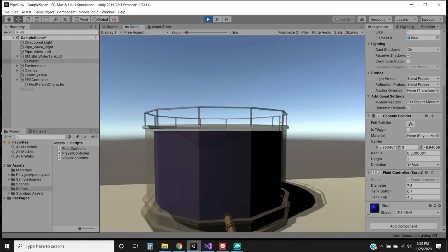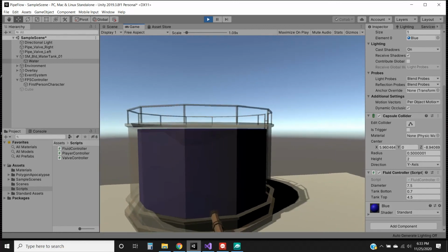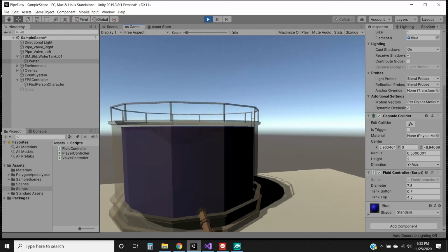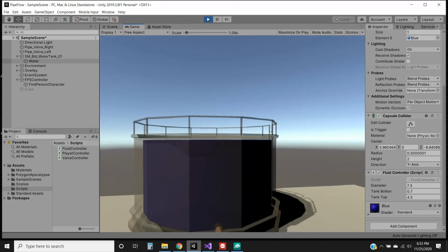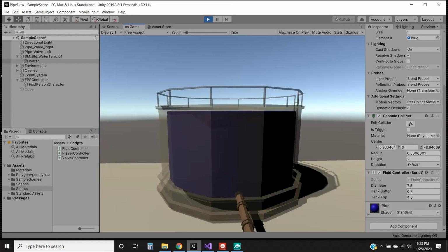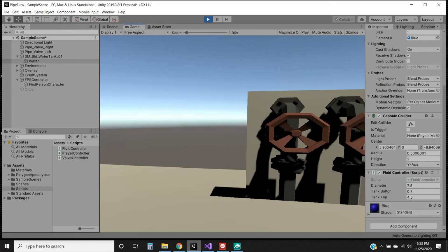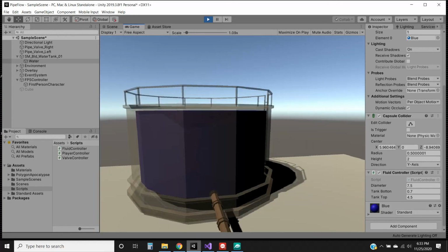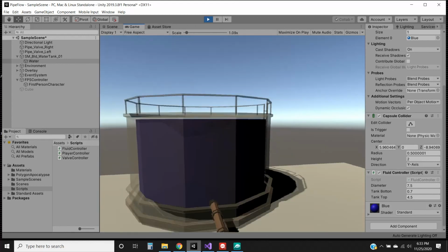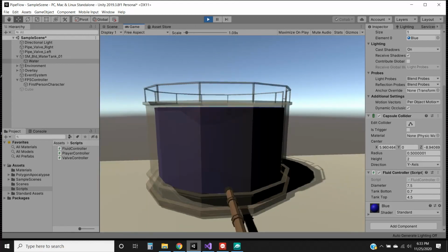One thing about this flow rate is that it's volumetric flow rate with constant head. So basically our flow rate is not changing at all during the course of this tank filling up. And that's a reasonable assumption, I think, when you have a city, municipal distribution system supplying your flow, because it's going to stay relatively constant, and you have this reasonably small tank here.